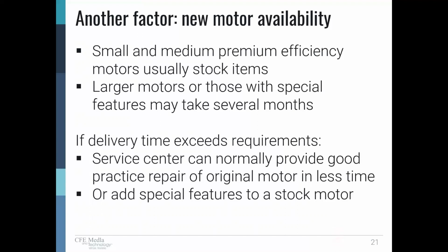And they may also be able to add special features to a stock motor. Maybe they can retrofit it. Maybe the customer, the end user, needs to have a C face on the motor, and the service center can get a C face flange from the manufacturer, take off the normal end bracket and put the C face end bracket on the motor. So again, that's modification. So in the service industry, we may be able to change that new motor into what the customer can use.